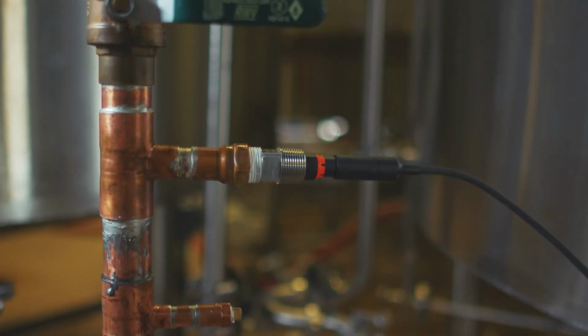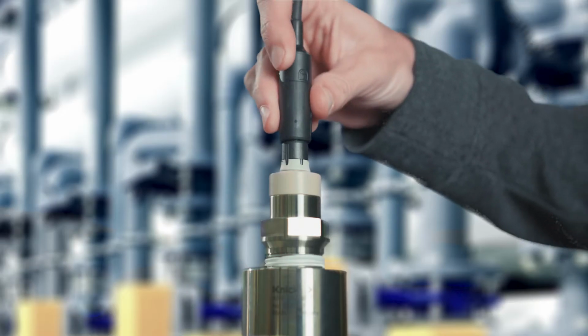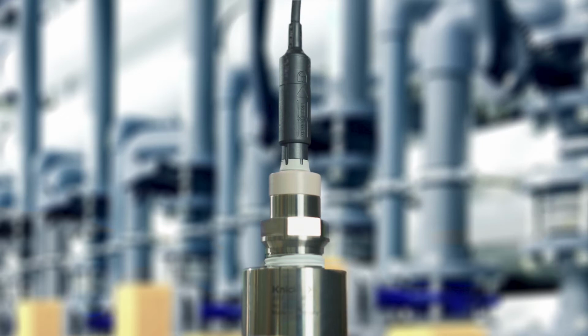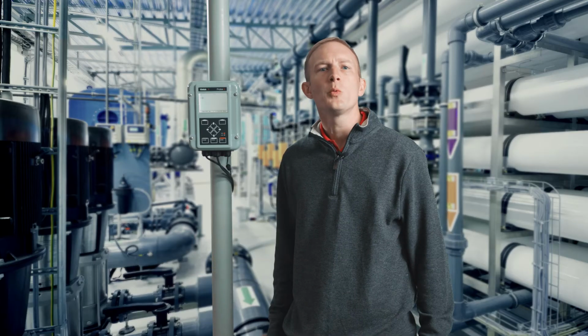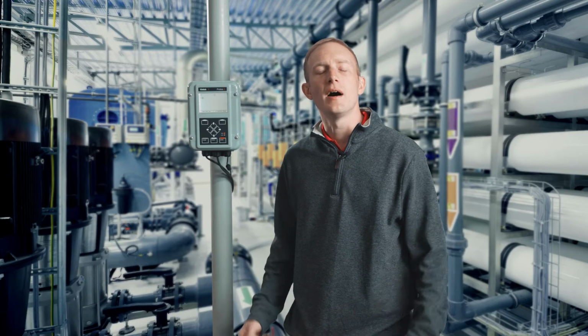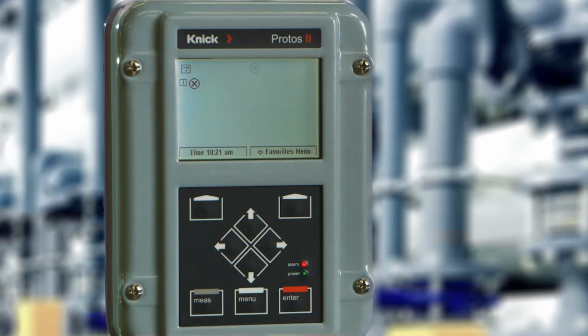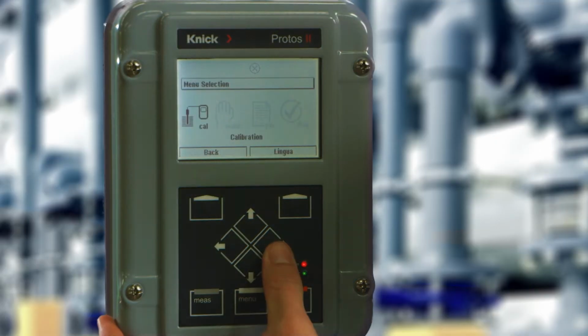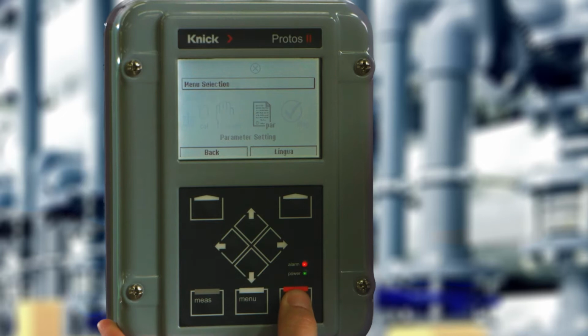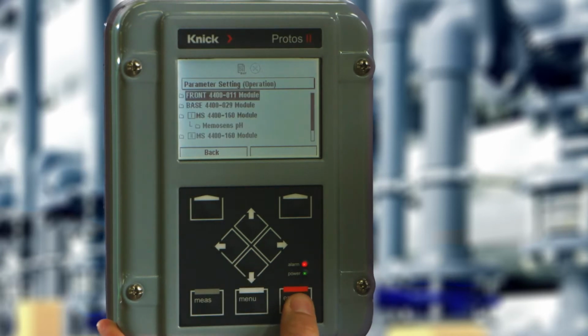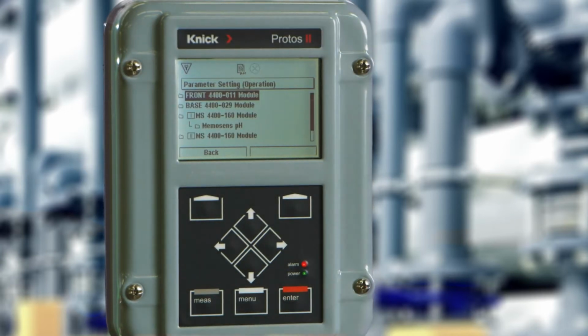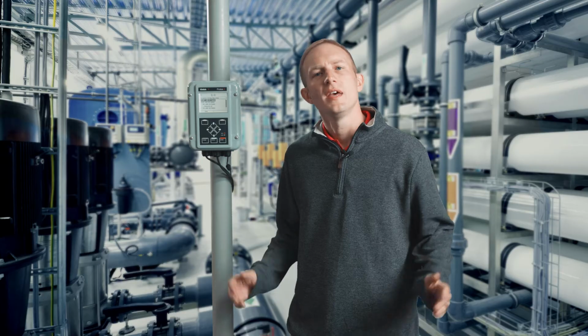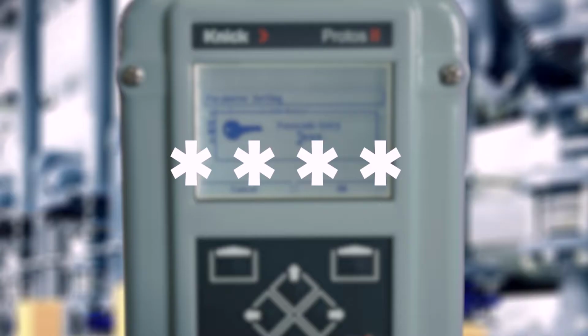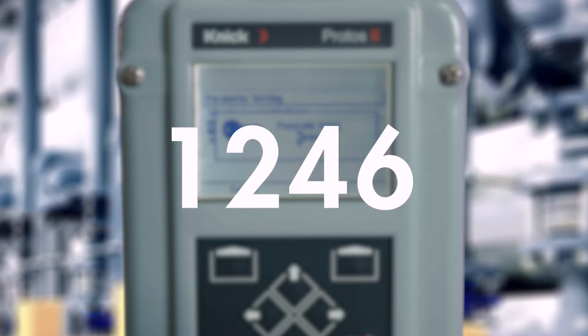Let's begin by connecting our MemoSense pH and conductivity sensors and configuring our Protos for a dual channel measurement. To get started, we will need to enter the operator level of the parameter setting menu. First, press the menu button and then toggle to the right to parameter setting. Scroll down to operator level and press enter to go into the menu. If prompted for a passcode here, please note that the default is 1246.